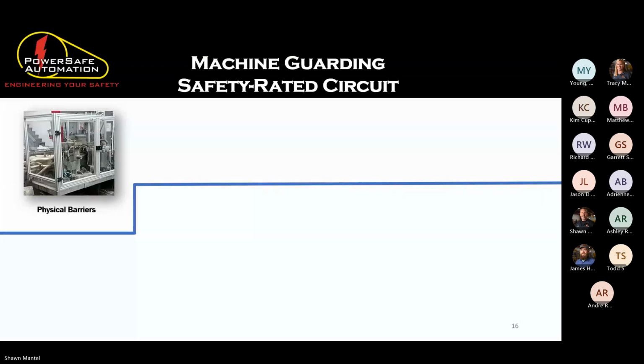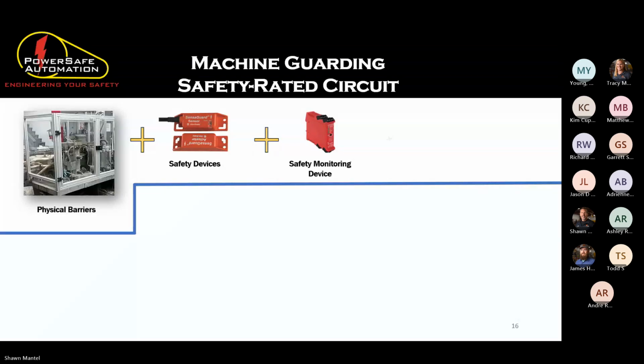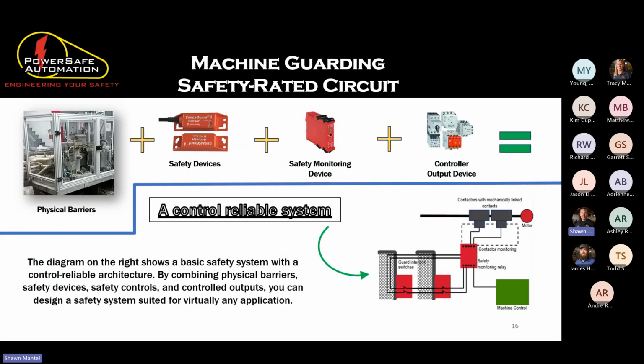So you have your physical barriers, then you have your safety devices, then you have your monitoring devices, then you have your control output devices. Could be a contactor, could be a drive motor, whatever that is. And this right here will then give you a control reliable system. It's all determined on what components you use, how you wire it, where everything is located, other components on your machines, the type of output devices you are using will determine what category level of that reliable system. But with the physical guarding, using the correct safety devices, not just a blade style mechanical switch, and you're monitoring properly, you're not sending the switch straight to an emergency stop, and you're not not monitoring it, and you have the right controller or the right output devices, then you can have a reliable control system.